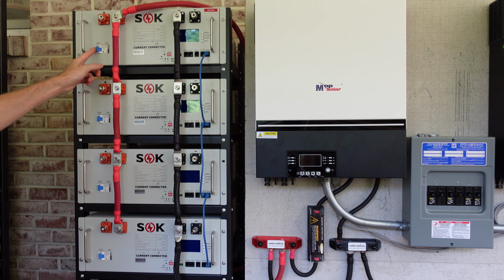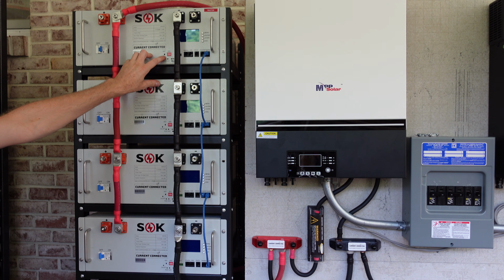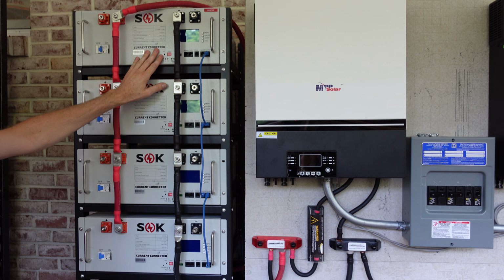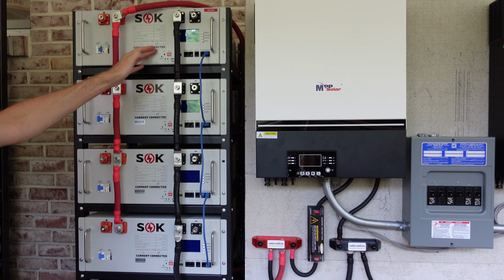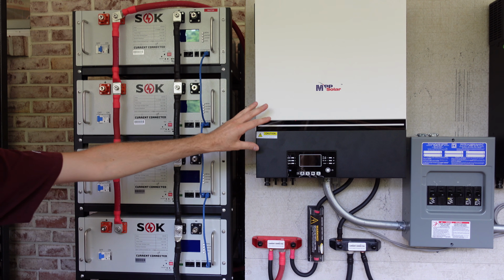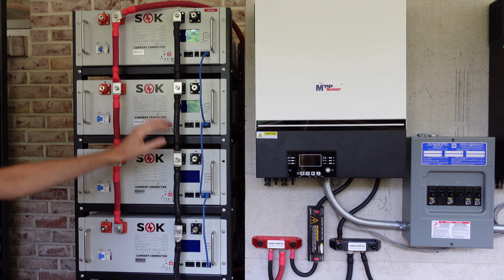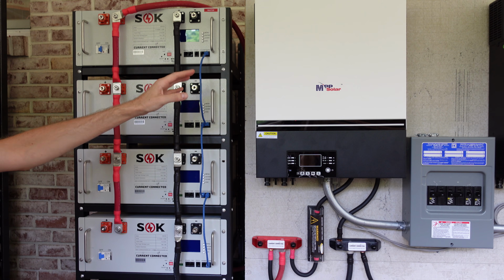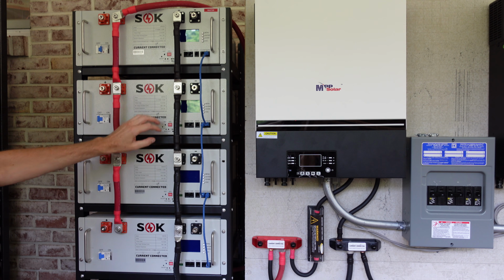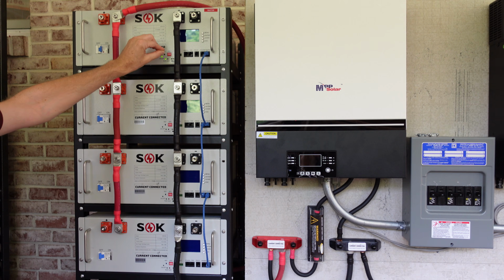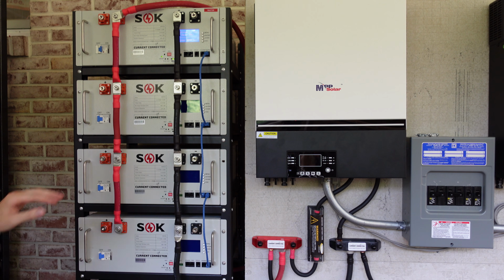I'm going to flip one of the circuit breakers on. I'm then going to press in on the reset button of the top battery, and that will begin starting up the battery and will also engage the pre-charge circuit in the battery to pre-charge the capacitors of these inverters, which will avoid a large inrush of current if you were to just flip the circuit breaker with the BMS already turned on. And you heard it made a click noise. That was the current flowing and charging up those capacitors.